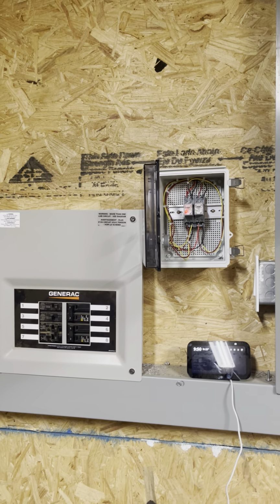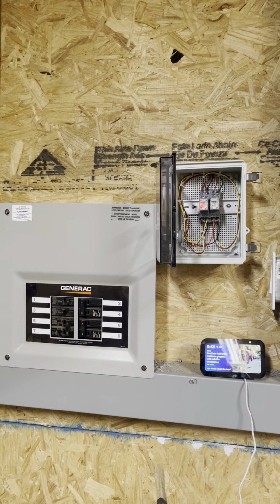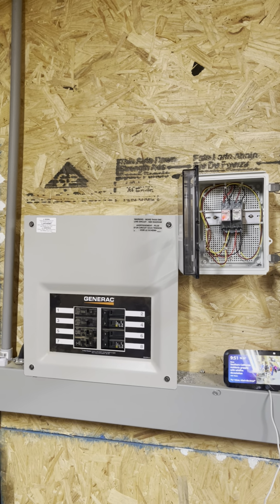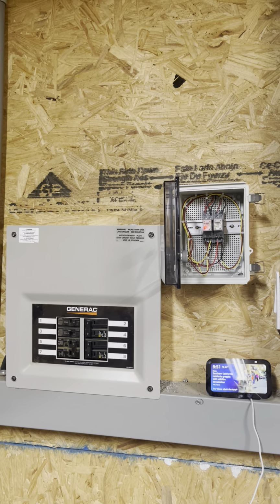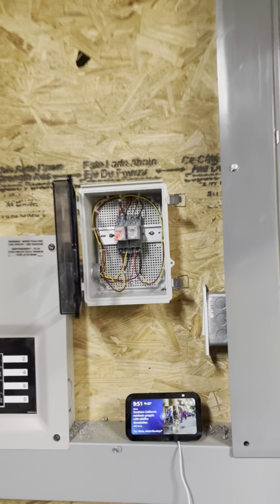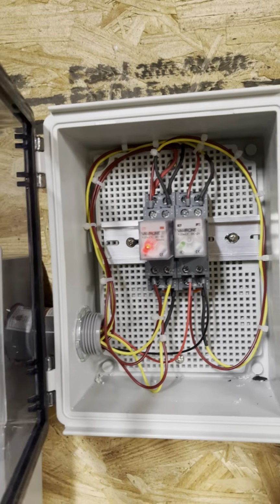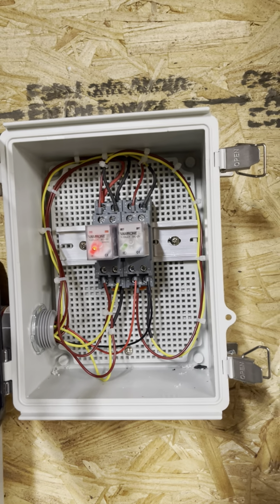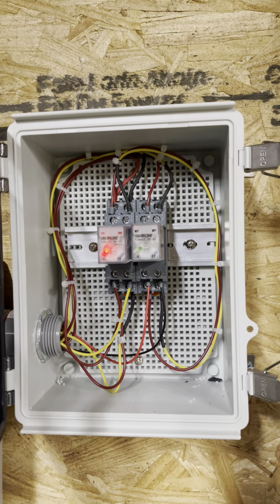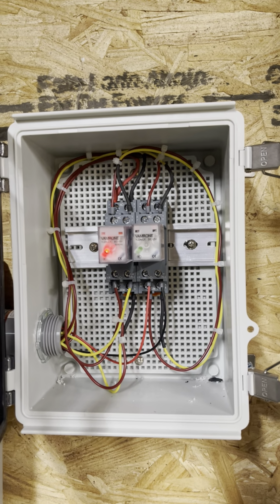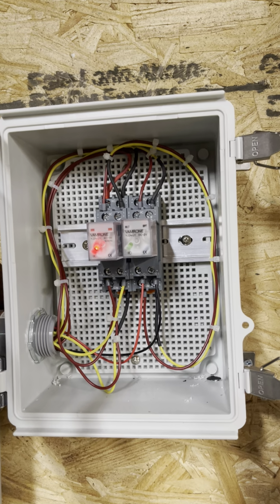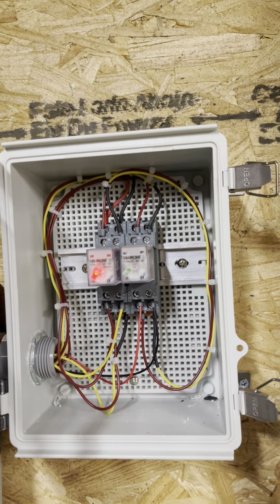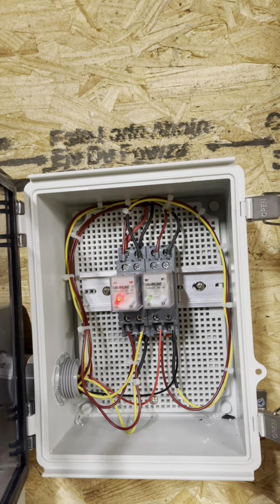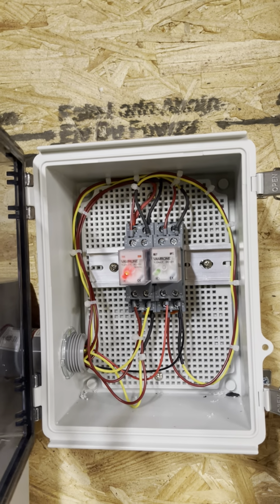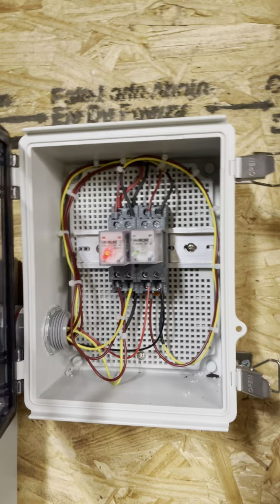Once the batteries get full up to their set point, which I think I've got set at like 53.5 volts or so, it says, hey, my batteries are full, I can run off of battery, and it triggers the relay to shut off. When it does that, it actually lets the generator think that it's receiving power, because when it triggers that relay, it turns on the power from the solar side, and so the generator will go into its cool down cycle and shut off and wait for the next event to happen. The other nice side effect is, from across the room, you can see the red light is on, and if the red light is on, I have grid power for backup.